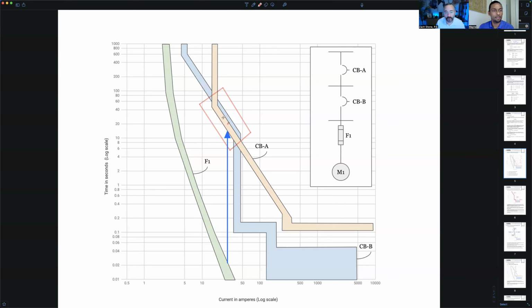We want to get everything from A to the right and above of everything in blue from circuit breaker B. That way, if I've got this fault current right here, B is going to trip before A. Maybe that fault current is downstream of B, right? Here's our fault. And we want B to trip.